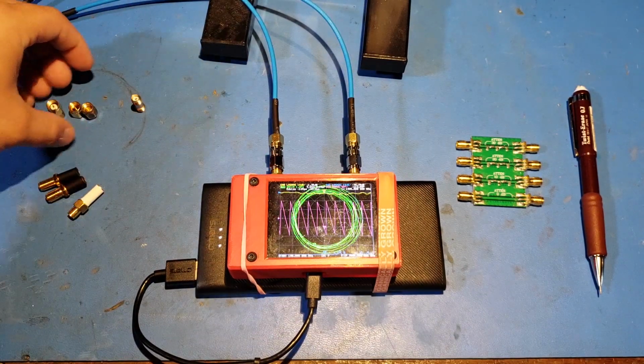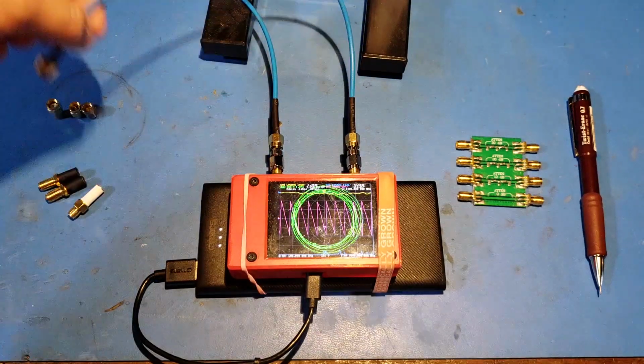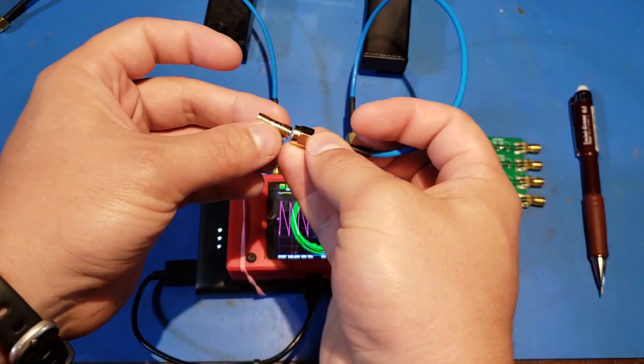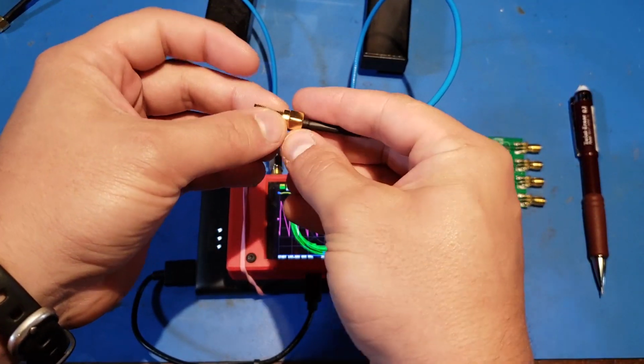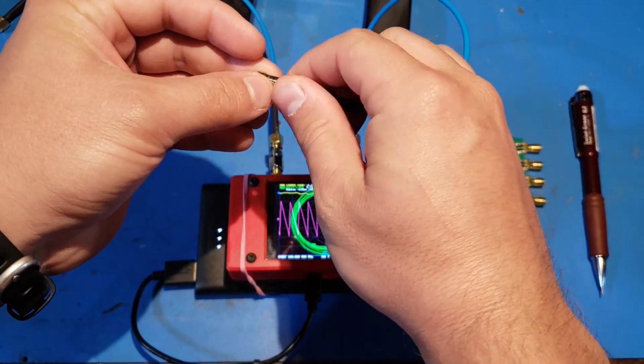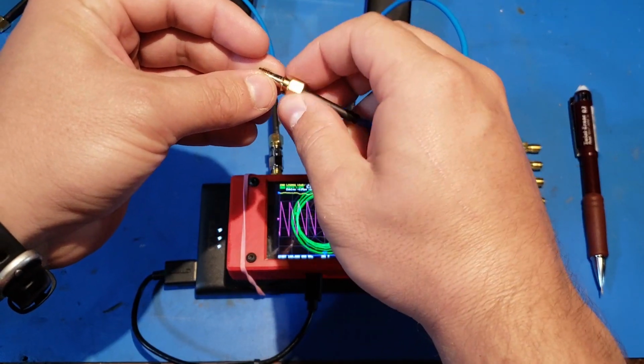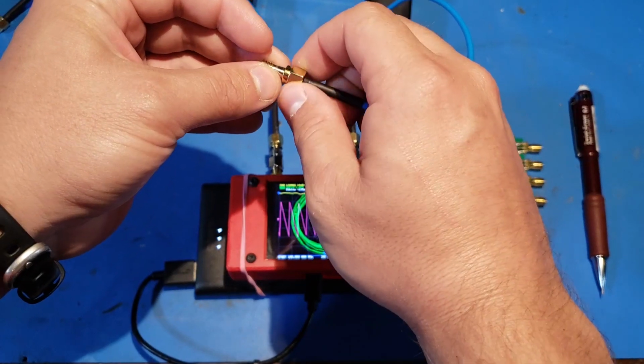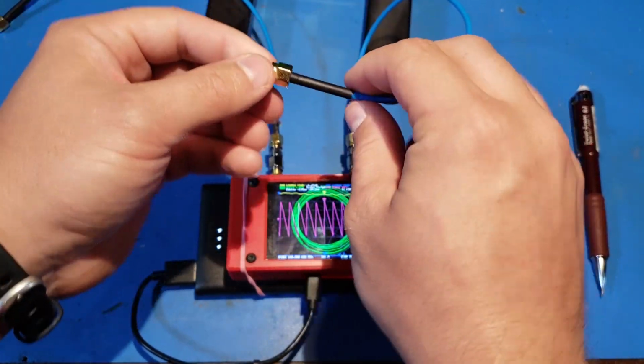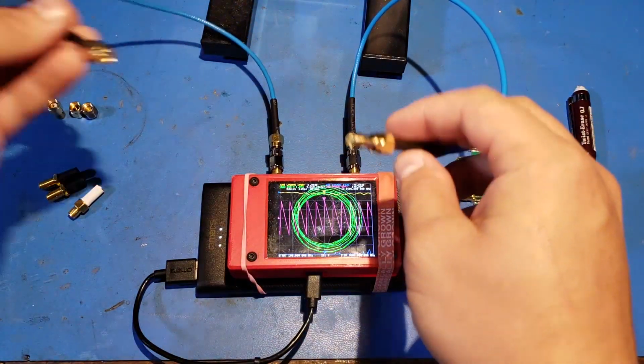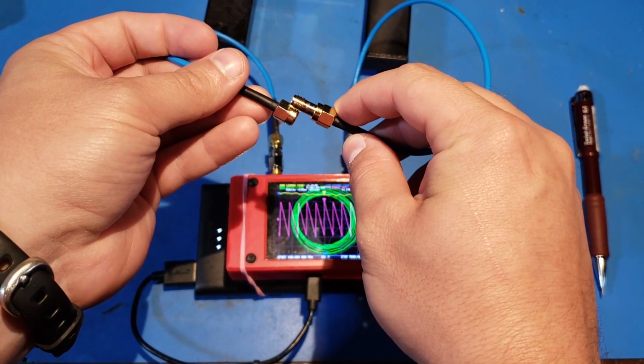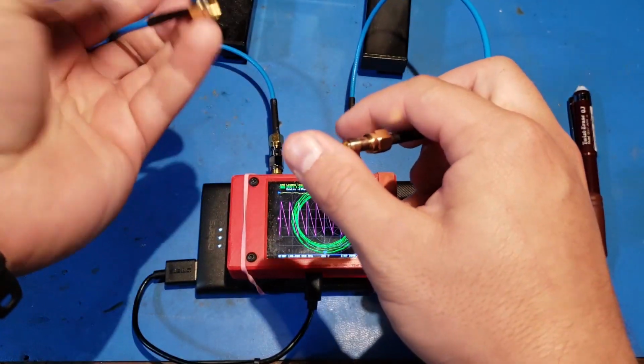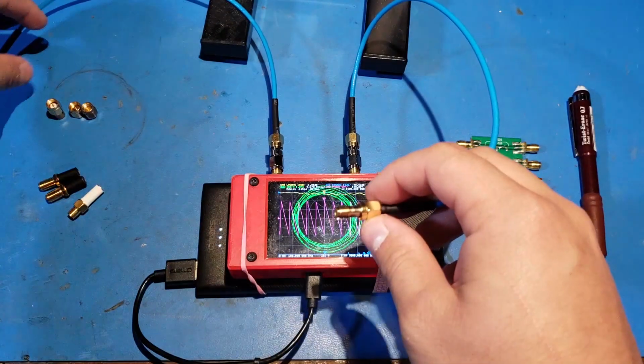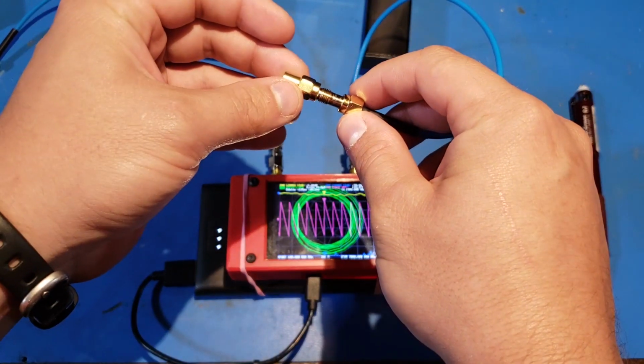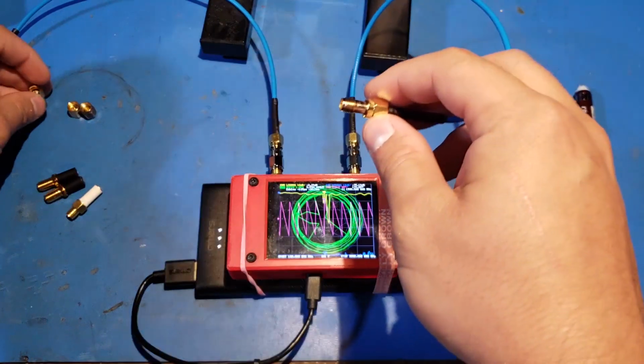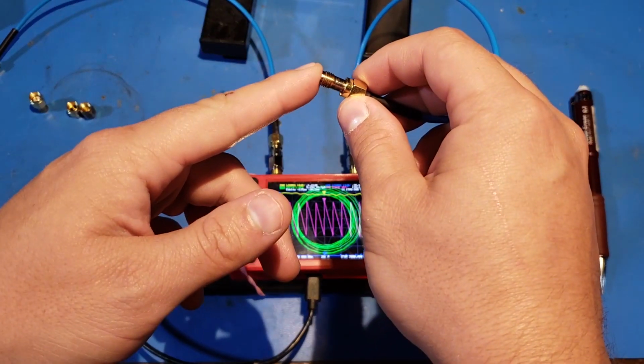So when you make your calibration, you connect the male SMA connector of this cable to the female-to-female adapter like so, taking care to not spin the wire and not spin the adapter and let that go straight in while you spin the outside of the SMA connector. And then when you make a through measurement, you connect this SMA connector right to here for no through standard at all, since this will be your measurement plane. And for each standard, you connect your load, short, and open to the end of this connector.